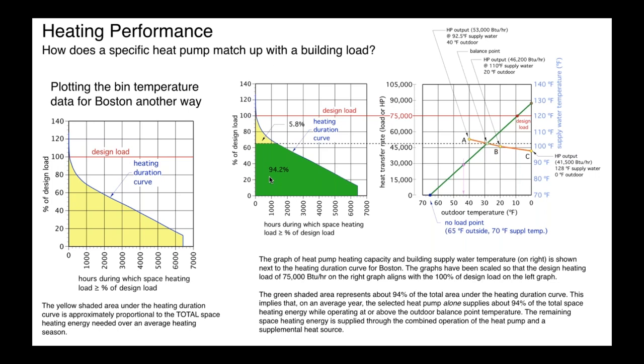And this surprises some people, all right? The capacity of this heat pump is not 75,000 BTUs per hour. Again, its capacity is a strong function of outdoor temperature, but let's say in nominal terms, it's about a 4-ton heat pump. So it's around 48,000, 50,000 BTUs per hour nominal. And you might say, well, why would anybody put a 50,000 BTU per hour heat pump into a building with a design load of 75,000 BTUs per hour? That's grossly undersized. Well, yes, for a boiler, it probably is, but because of the combination of the outdoor temperature ranges we're working with and how that affects the performance of the heat pump, we're still looking at a situation where that heat pump is supplying the vast majority of the total space heating energy.